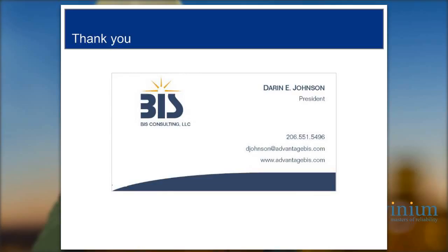Thank you, Darin. Yes, we have received some questions from our audience, and the first one we will ask is, what is your view on testing? So testing fits in pretty well in this kind of an analysis. You can do a cost-benefit evaluation of testing by asking yourself, if I knew this cable was in bad condition, how would that change my decision about whether to replace it or inject it, for example. And so you can treat cable testing as an intervention to be evaluated, and treat the benefit of testing as the information that you get, the reduced uncertainty that you'd have after the test was completed.